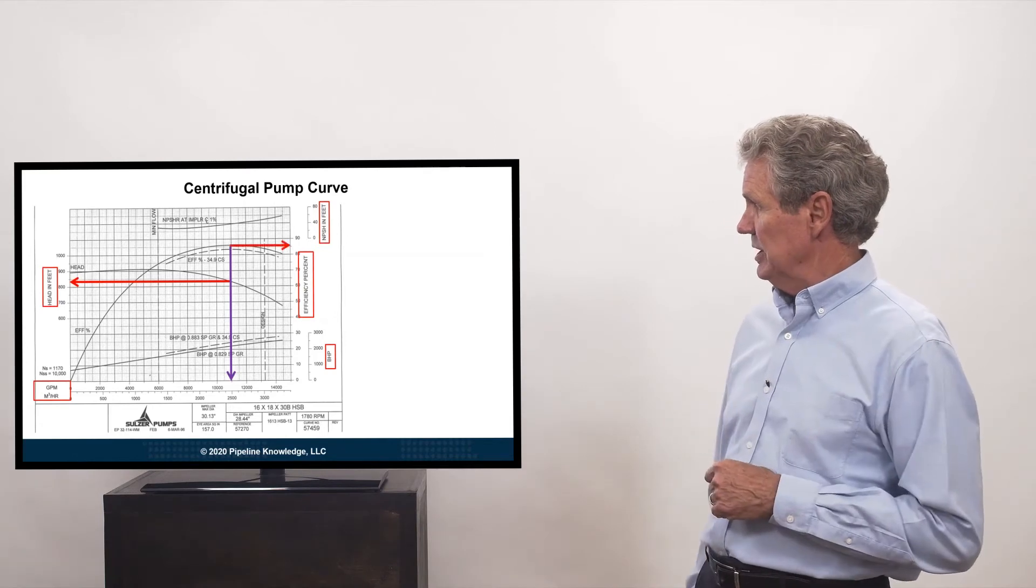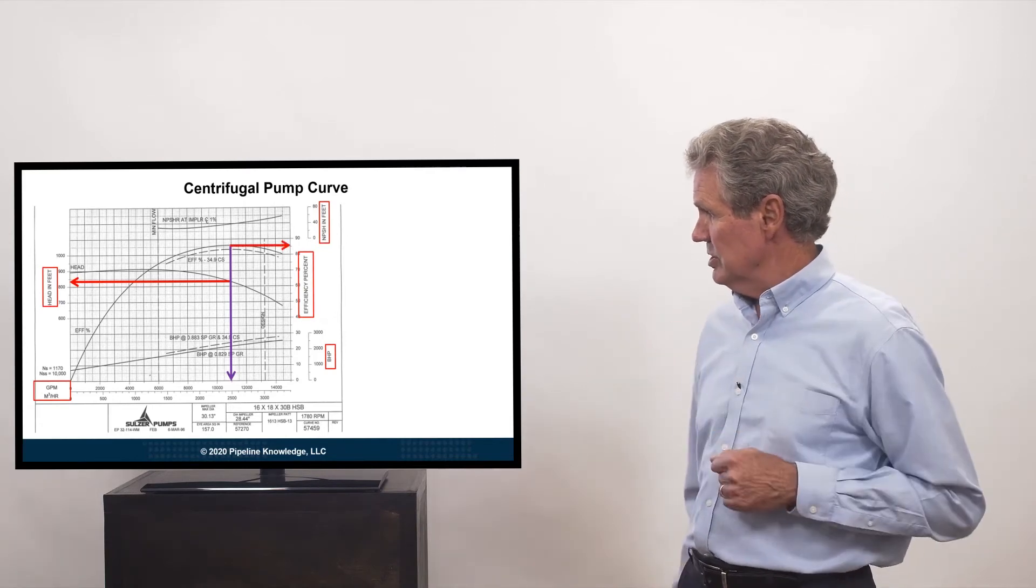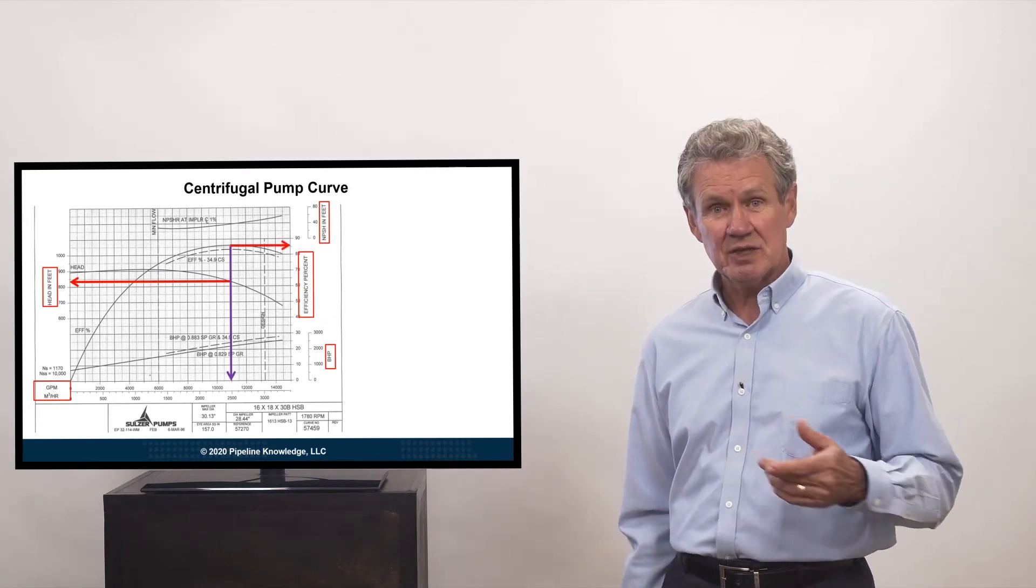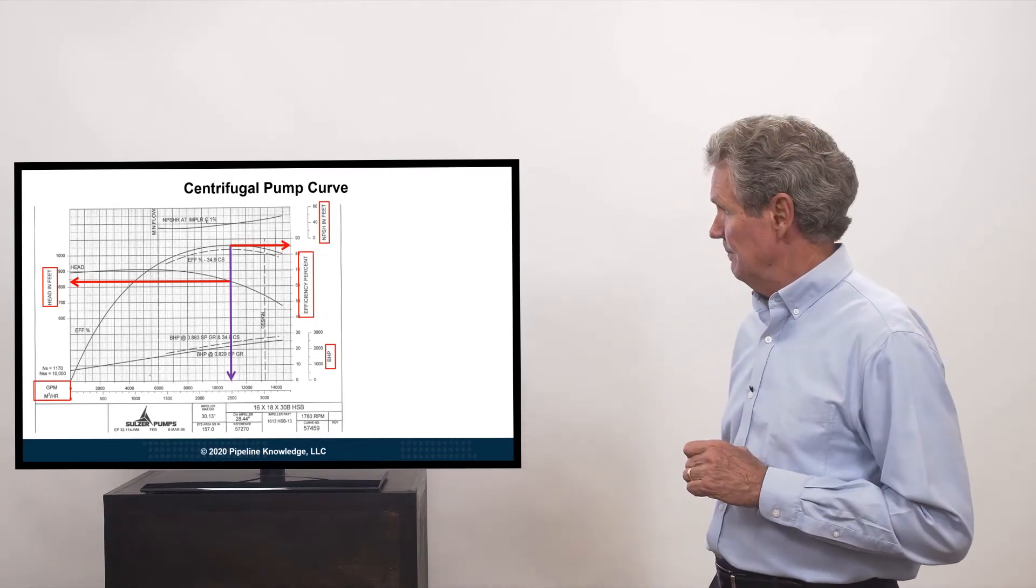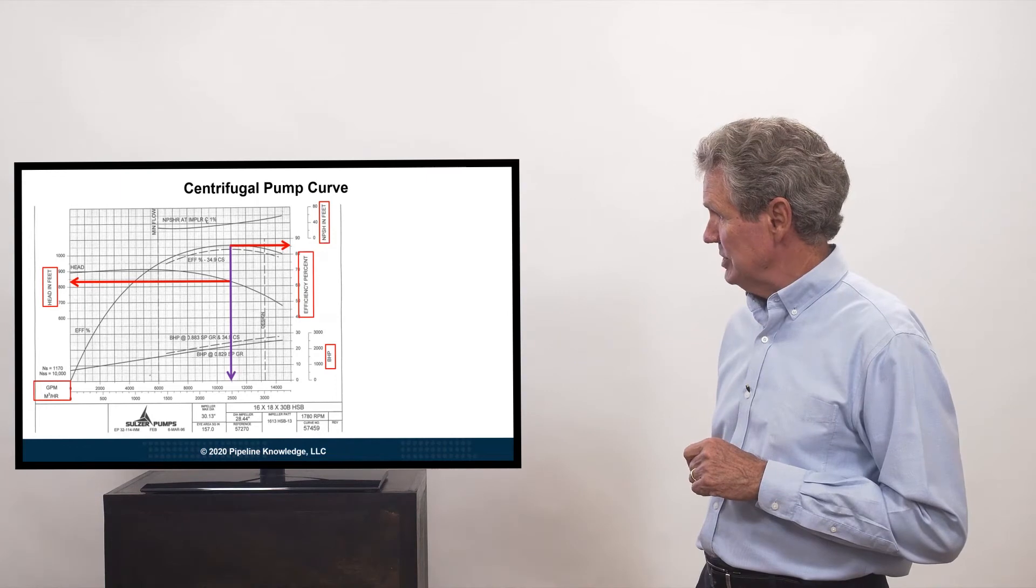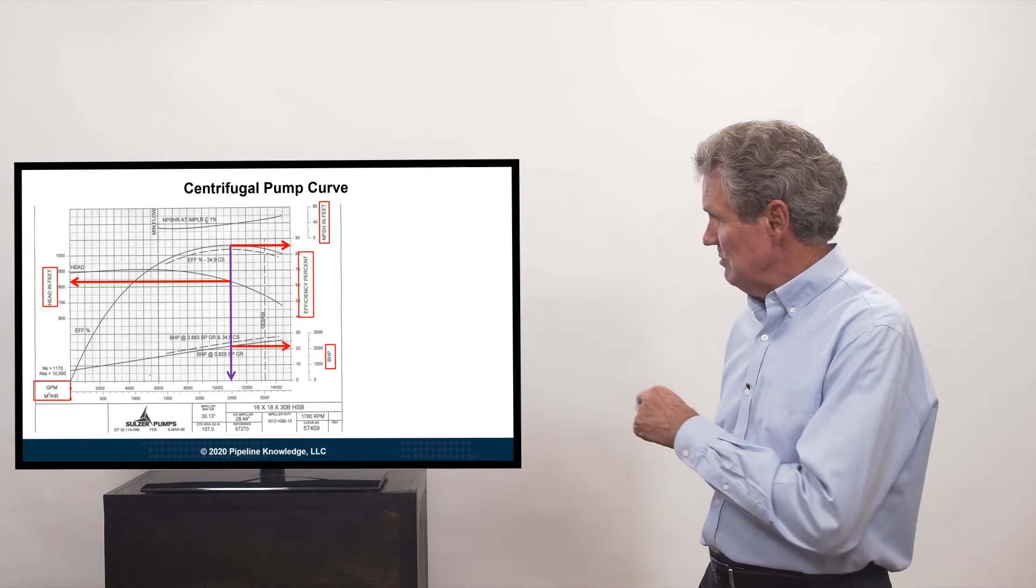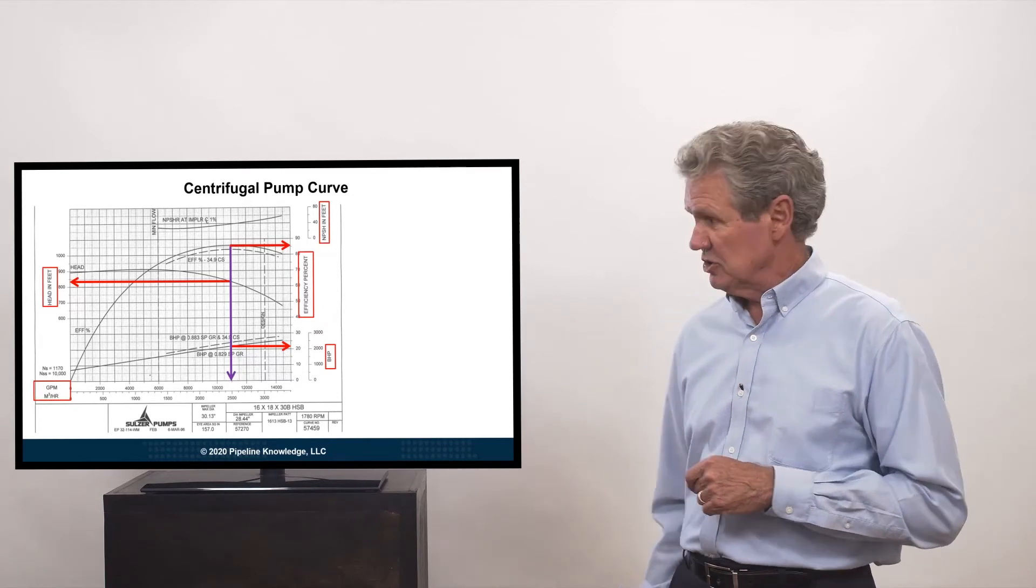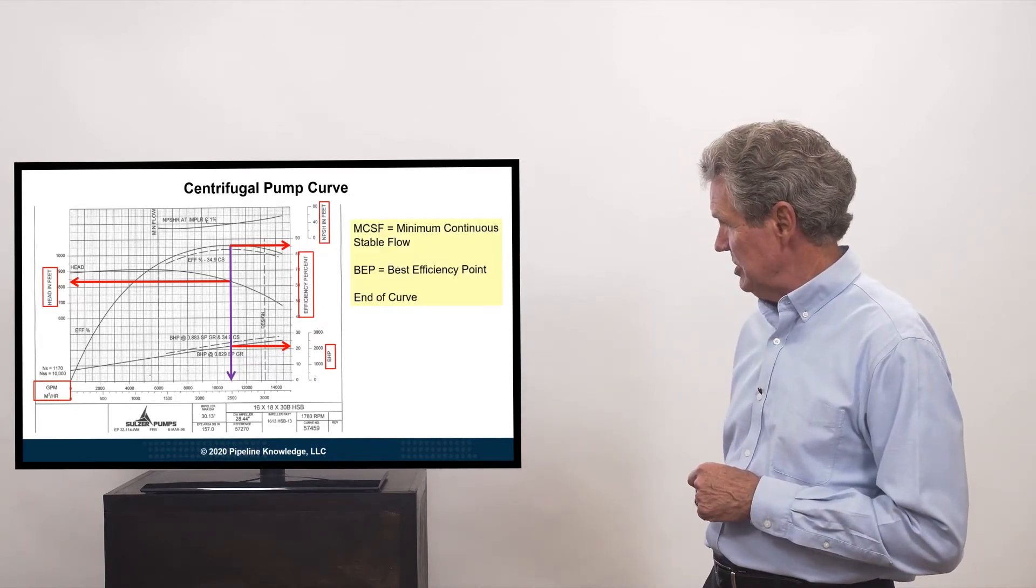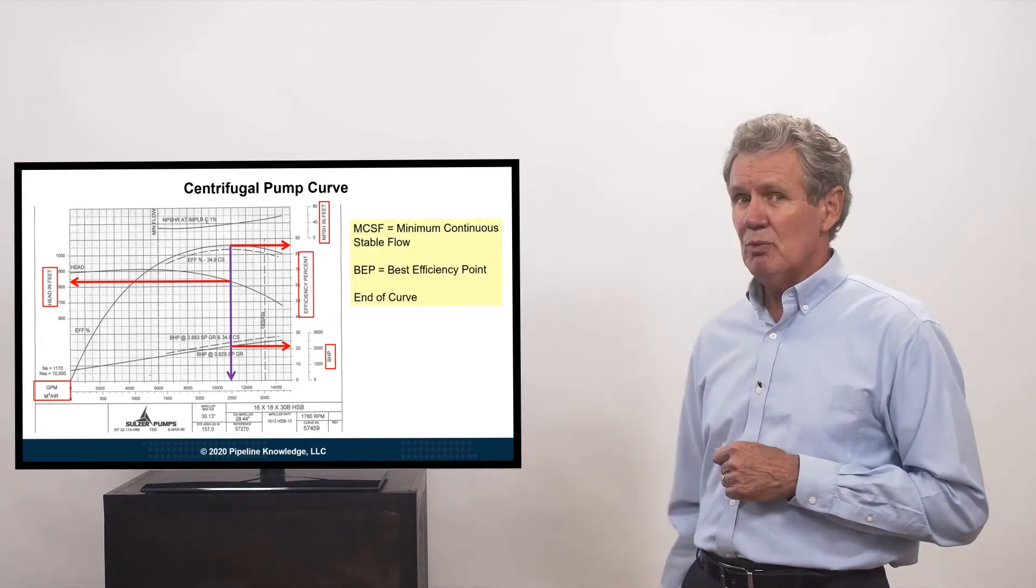Reading up the purple arrow, then, we can read across to the efficiency curve. It tells us what the efficiency is at that particular rate and that particular pressure. And then, we can also read over to what the brake horsepower is. A lot of interesting information here.